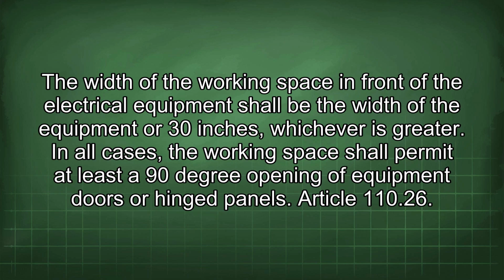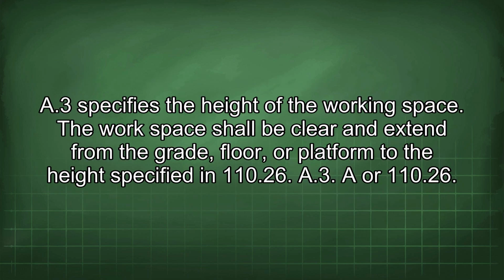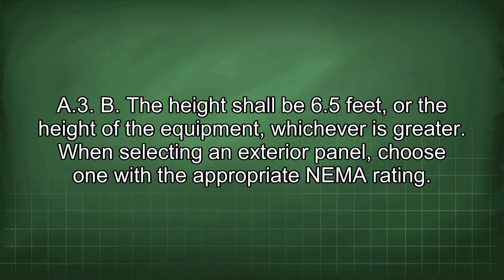Article 110.26 A3 specifies the height of the working space. The workspace shall be clear and extend from the grade, floor, or platform to the height specified in 110.26 A3 B. The height shall be 6.5 feet, or the height of the equipment, whichever is greater.